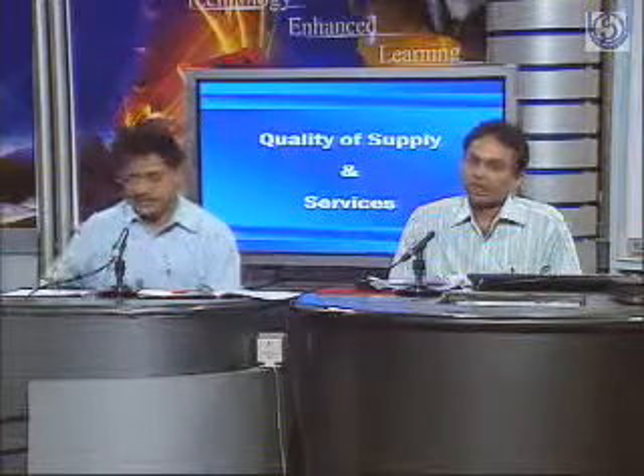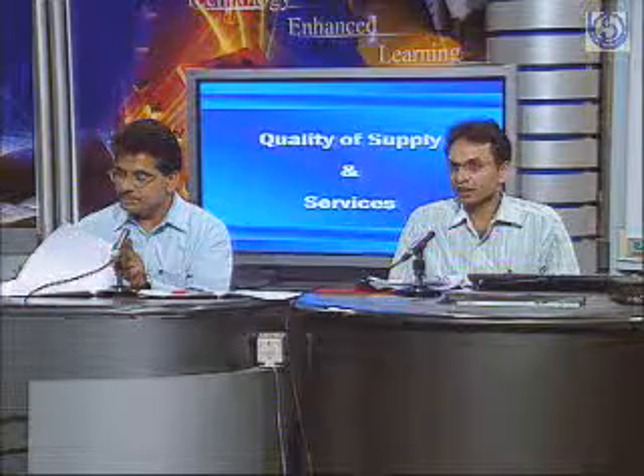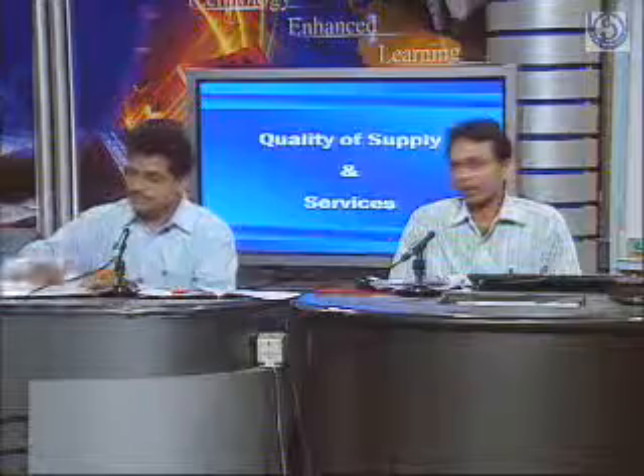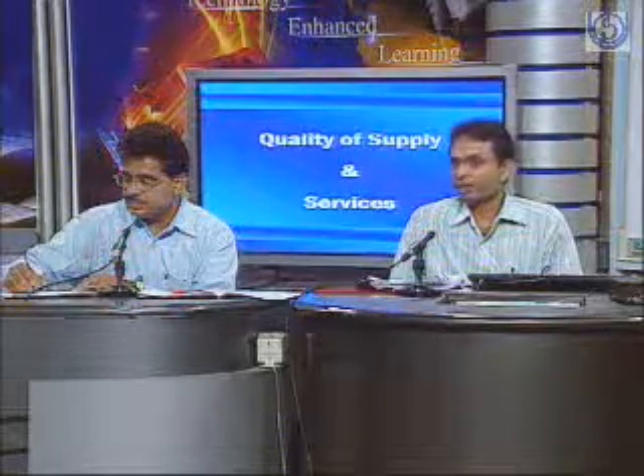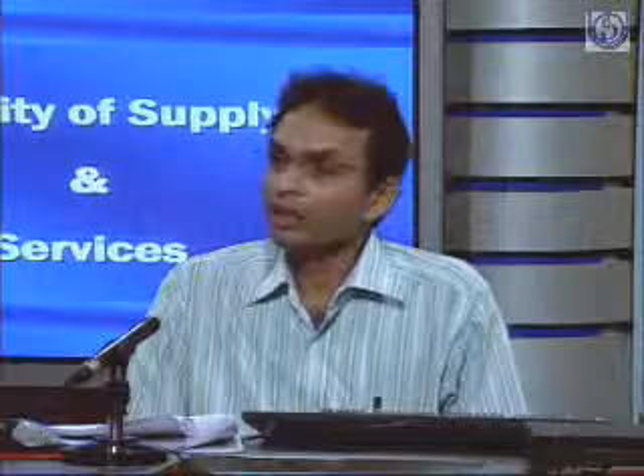Over, sir. For testing, there is a provision in the Indian Electricity Rules. Rule number 57 clearly specifies the testing. According to that, if the meter is at high tension level, say 11 kV and 33 kV, then the meter has to be tested along with associated metering apparatus, including CT and PT, in a span of 1 year - meaning those meters have to be tested on a yearly basis. If it is an LT meter, LT-CT operated meters, then those need to be tested once in a 3-year period, including testing of the CT. If it is whole current meters, whether single phase or 3 phase, testing has to be done once in a 5-year period. This is stipulated in the Indian Electricity Rules.